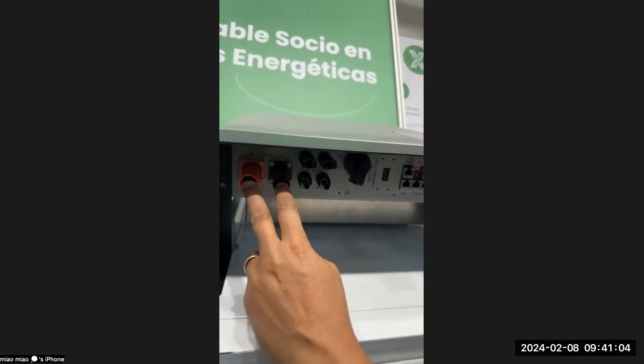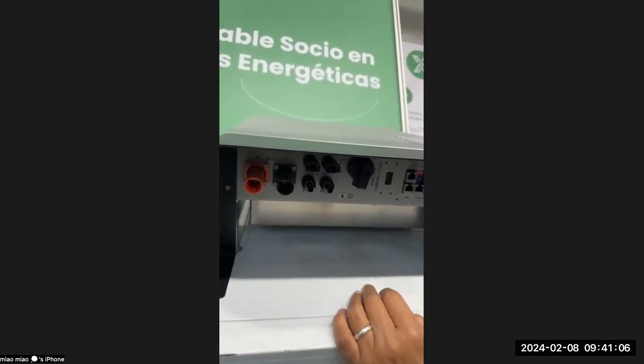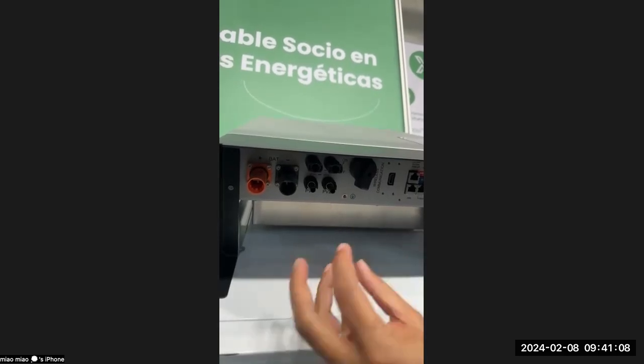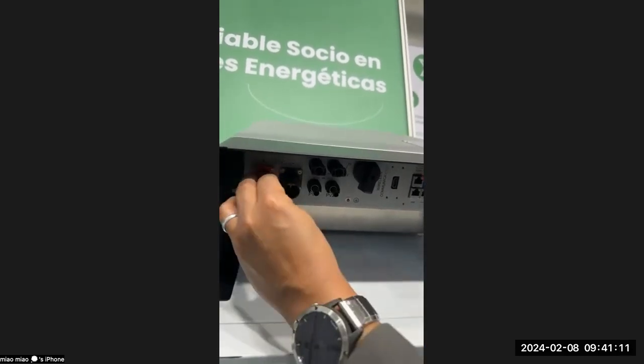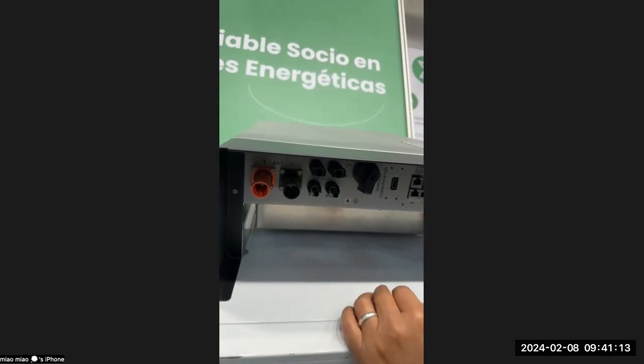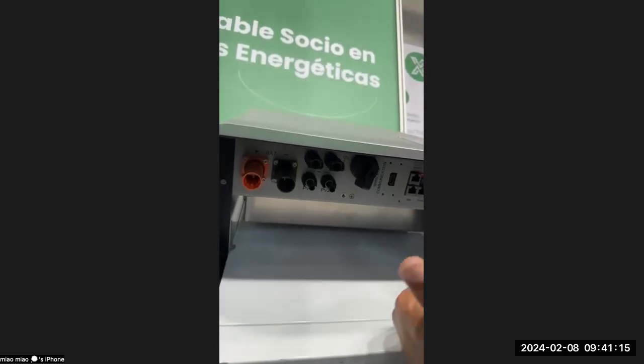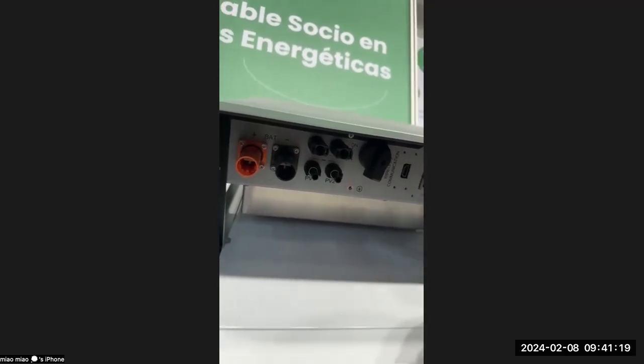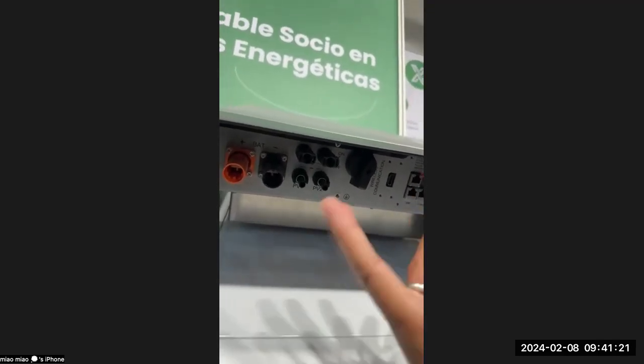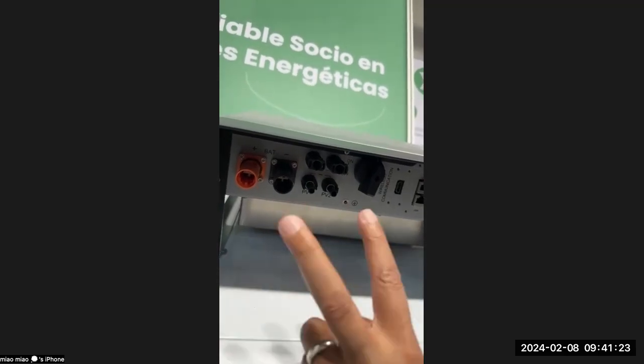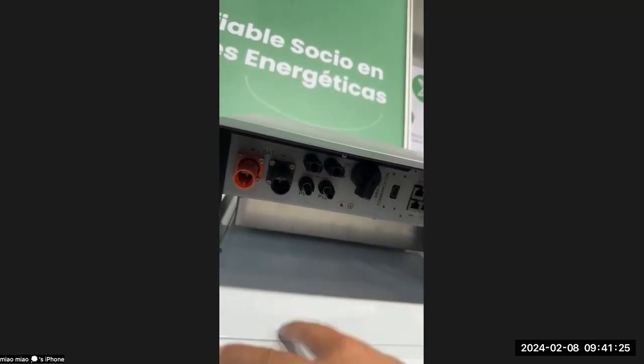We've color-coded the DC terminals for the battery, as well as the boots and shrouds that go over here, so that you can't get it wrong. If you are using a standard color cable, like we've seen some installations where the guys are using all blue or all black, you can get it wrong. So just make sure that you use your multimeter to measure your DC.